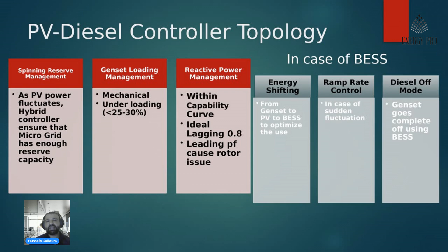Also, it will be used for ramping rate control in case there is any sudden fluctuation, any trip or a blackout from the generator or the PV. It will directly go to the battery and cover the load deficit. And also, with a battery energy storage system, we can have the generator off in case the loads are below 30%, and then it can shift to the battery and ensure that the load is supplied enough. So these are the six philosophies that the powerhouse controller takes care of in the case of the PV diesel supply.